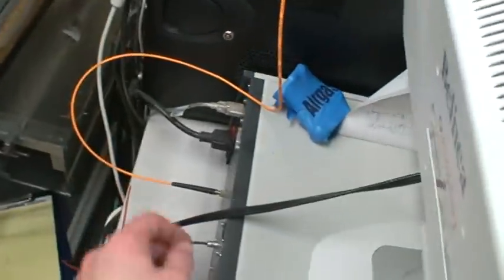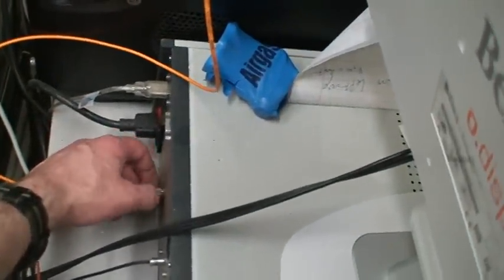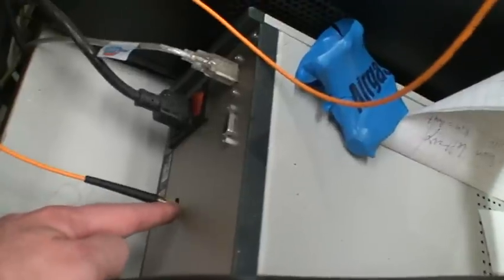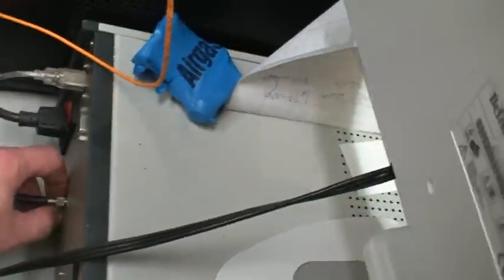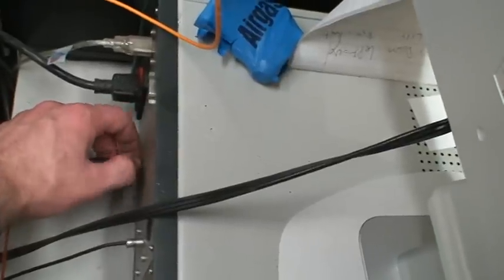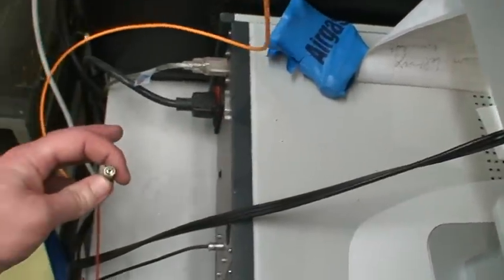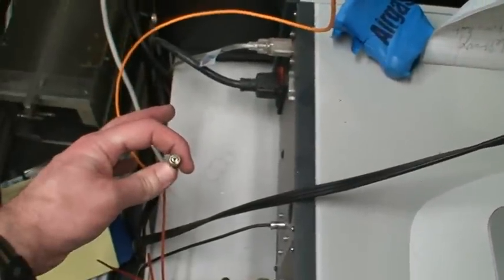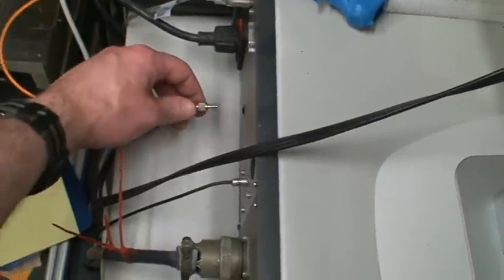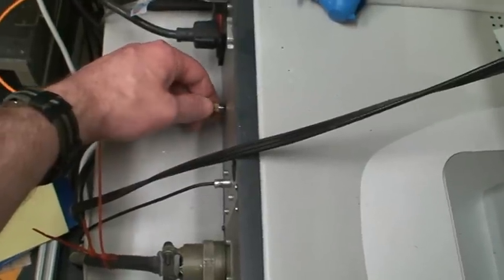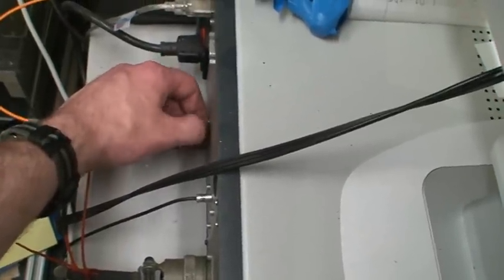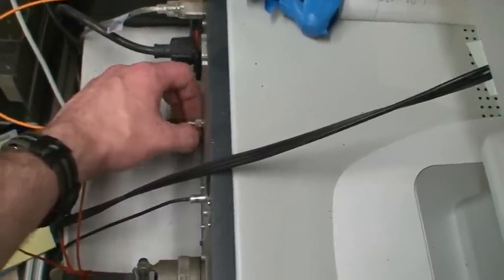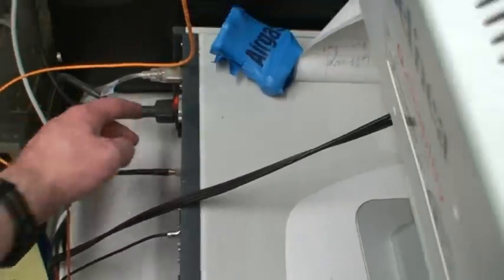It screws in—it's got a label of fiber on the back. This just screws in. You can see the glass filament inside of there if you look carefully. We'll stick it in and then just loosely tighten it. We can turn on the laser control unit.